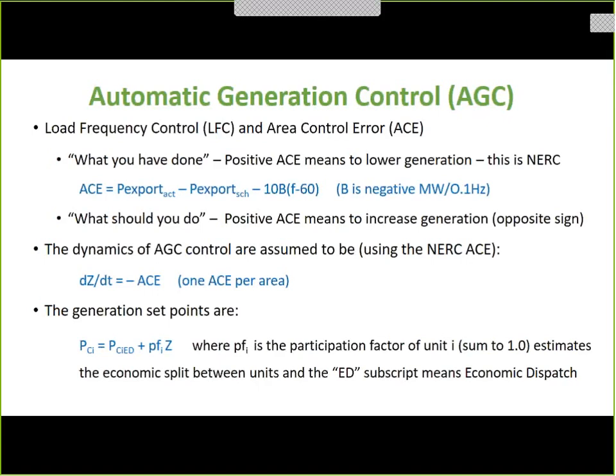If the frequency of the current goes far beyond what AGC is capable of, then something else kicks in? I don't know that it could ever quit. It will always continue to give you the signal to increase until something else blows. There's only last resort stuff like circuit breaker opening, tripping, things that cause blackouts.